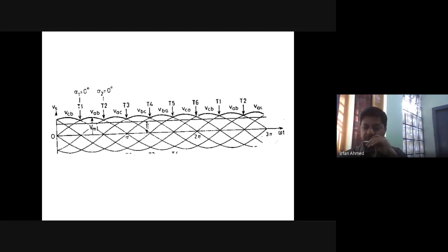Also, the output voltage is now much closer to DC compared to single phase rectifiers. This is why three-phase rectifiers are even better, giving a better DC voltage. In practice, in industry, you further increase the number of pulses, going for 12-pulse or 18-pulse rectifiers.